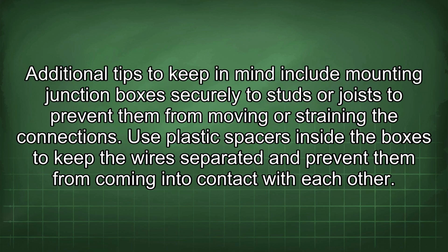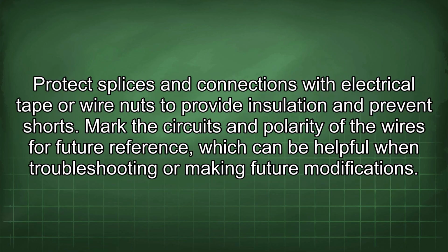Additional tips to keep in mind include mounting junction boxes securely to studs or joists to prevent them from moving or straining the connections. Use plastic spacers inside the boxes to keep the wires separated and prevent them from coming into contact with each other. Protect splices and connections with electrical tape or wire nuts to provide insulation and prevent shorts.